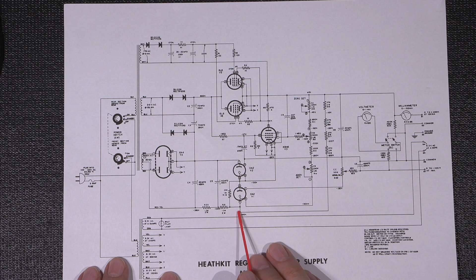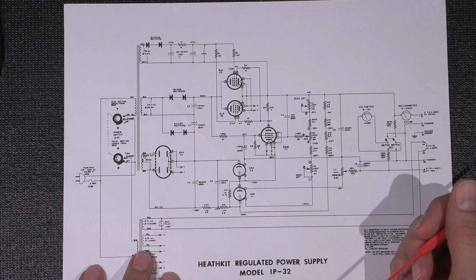So they have a bunch of protection devices here - you can see there's a jumper here as well. They want to make sure you're running this with both of those 0A2 tubes inside, so we have that nice stable reference here for this tube, so it knows where it needs to be to do its regulation.